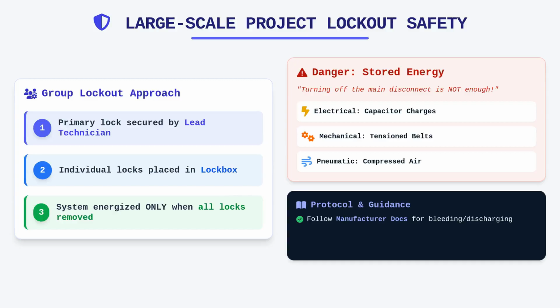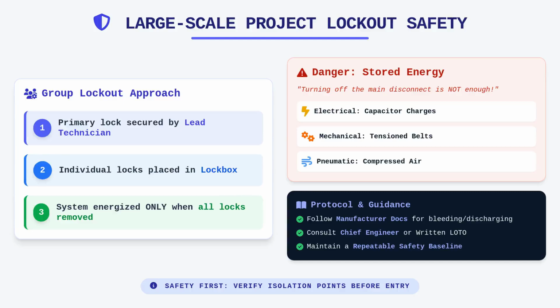Always follow the manufacturer's documentation for bleeding down pressure or discharging capacitors before you place your hands inside the housing or ductwork. If you are ever unsure about the isolation points for a specific piece of equipment, consult the facility's written LOTO procedures or reach out to the site's chief engineer. Documenting these specific steps for each unit is a best practice that establishes a repeatable safety baseline for your cleaning team.